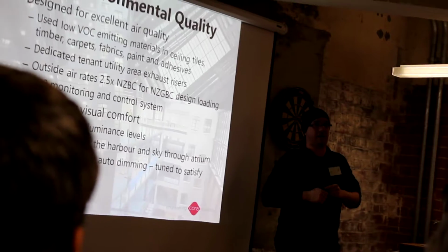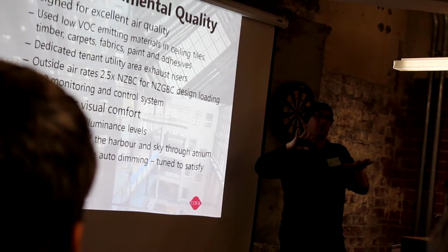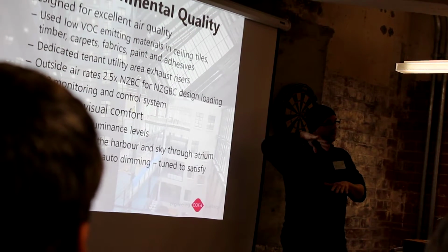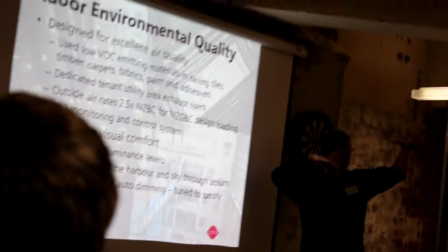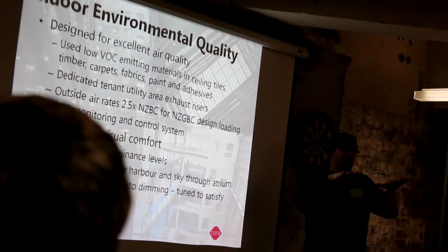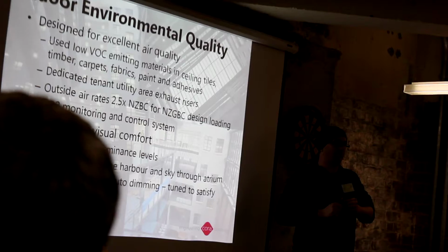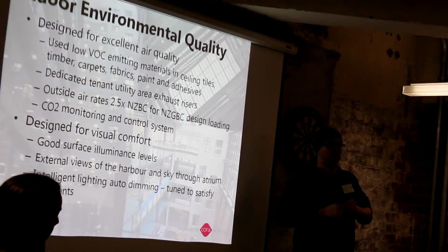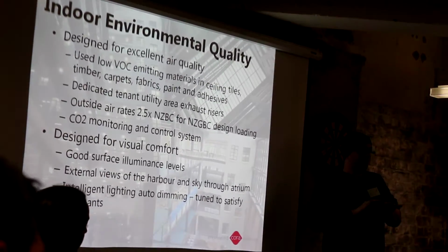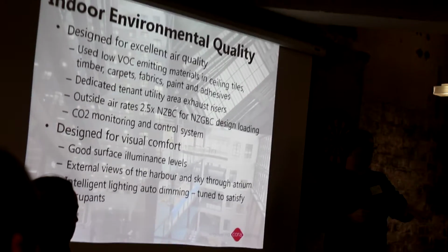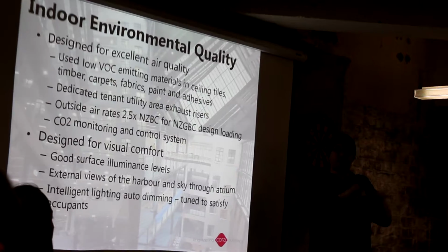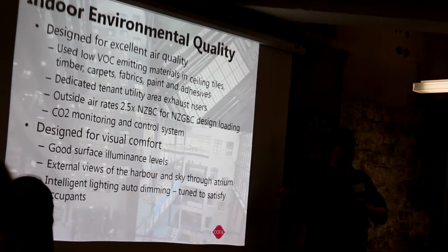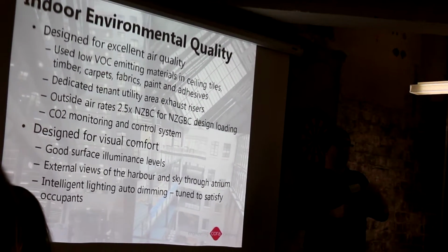One good example is we had an area of the building where we had a contrast problem. There's a lot of sunlight coming in from the atrium, and because of that, even though the light was tuned and commissioned properly at the right levels, it seemed kind of gloomy in that half of the building. So it was quite simple for Greg Blackwell in this case to go in and just change a few settings in the computer, bring the light levels up in that area of the building alone, and reduce the contrast, so everybody's happy with the light level now. We didn't bring the light levels up in the whole building, just that one area.